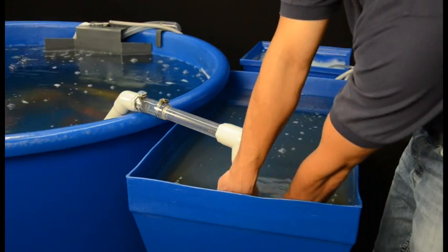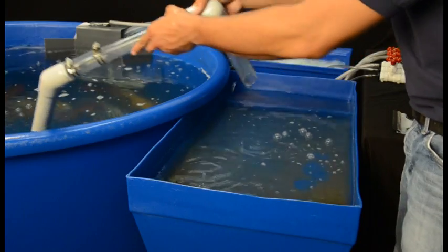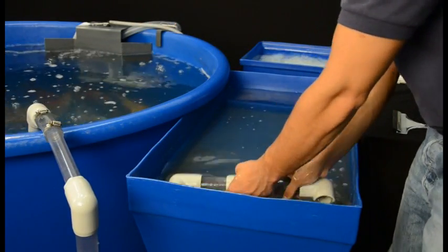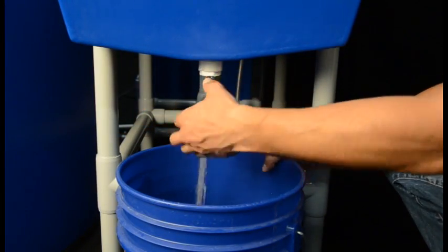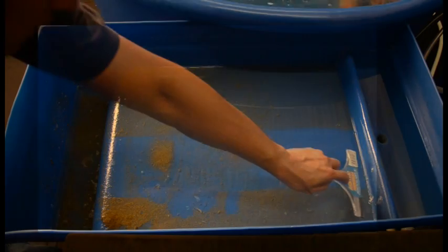To clean the clarifier table, you will have to stop the siphon from bringing water to the clarifier table. To do this, remove the siphon assembly connection from the velocity reducer. This will break the flow of water. Place a 5-gallon bucket below the ball valve drain of the clarifier table. Slowly open the valve. It is important to do this gradually or it may splash with the water that is draining from the clarifier table. Drain the table completely.